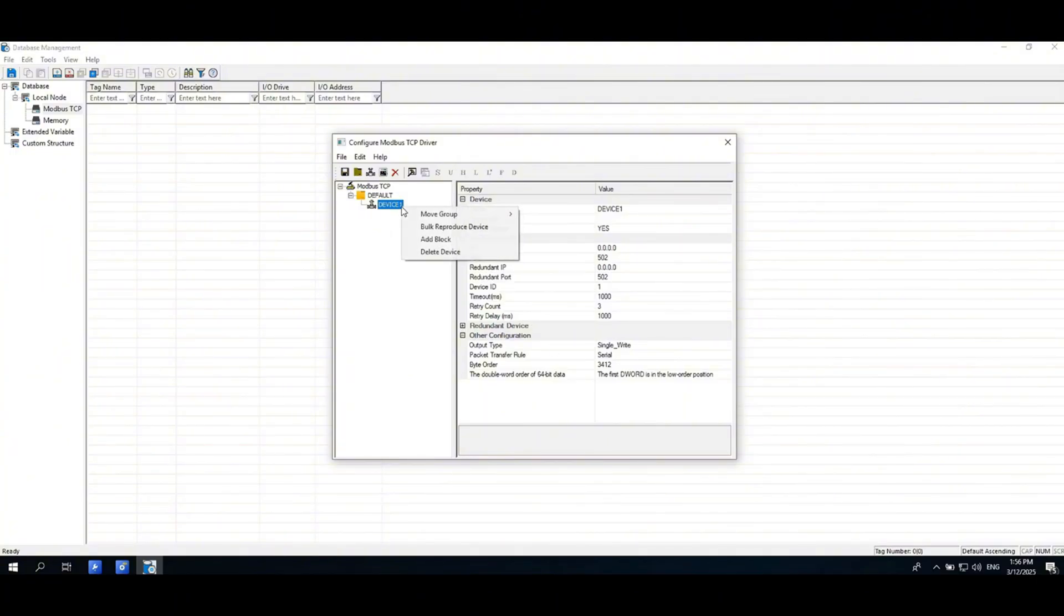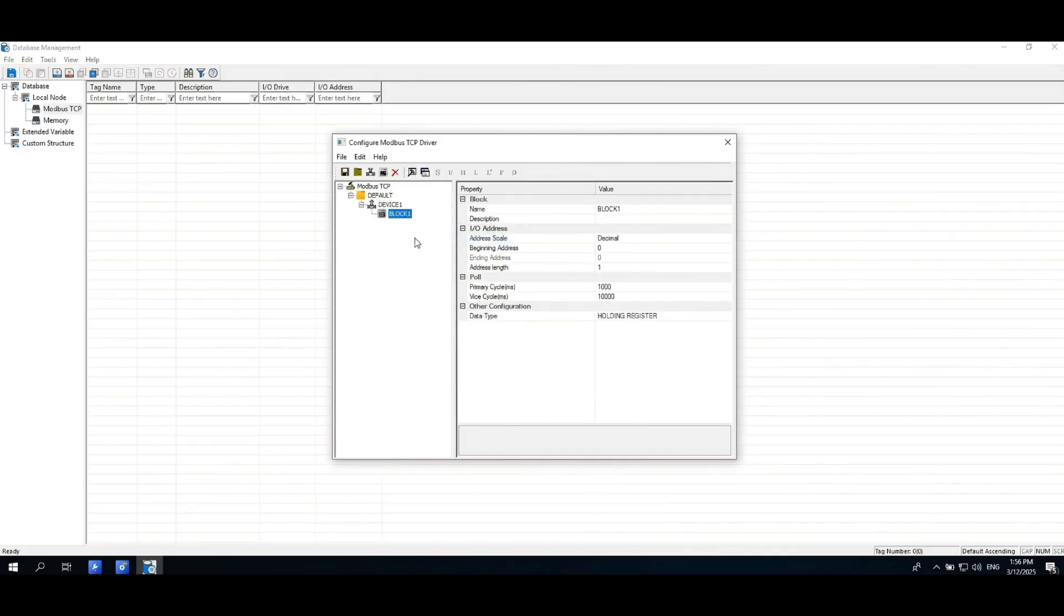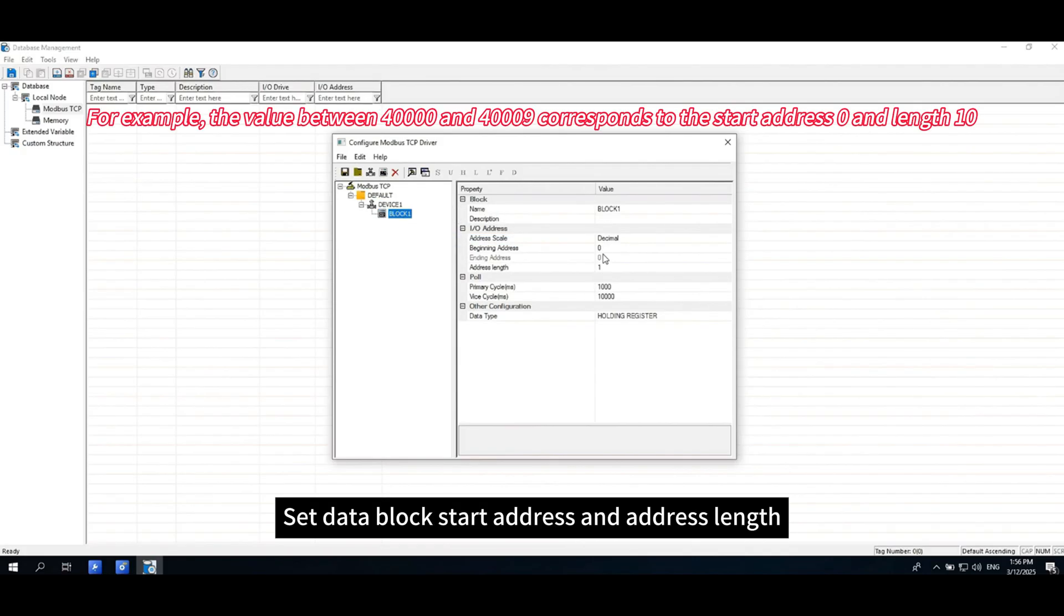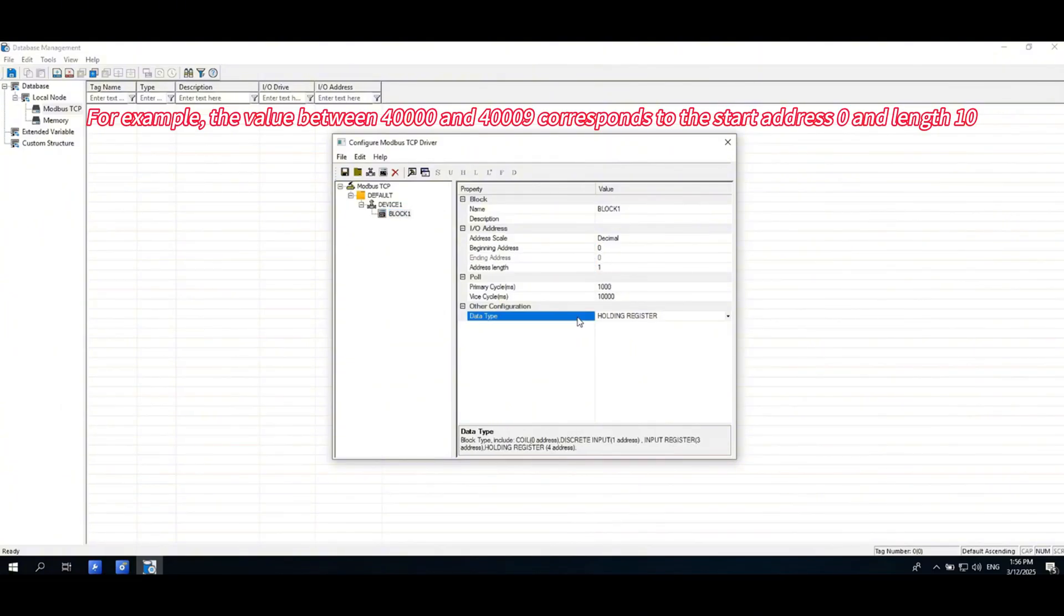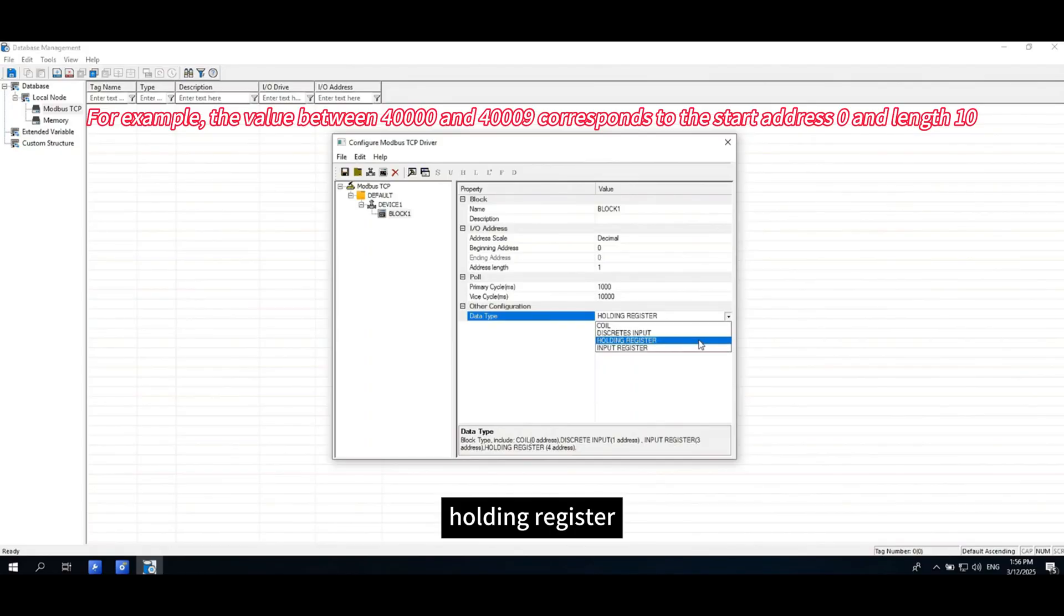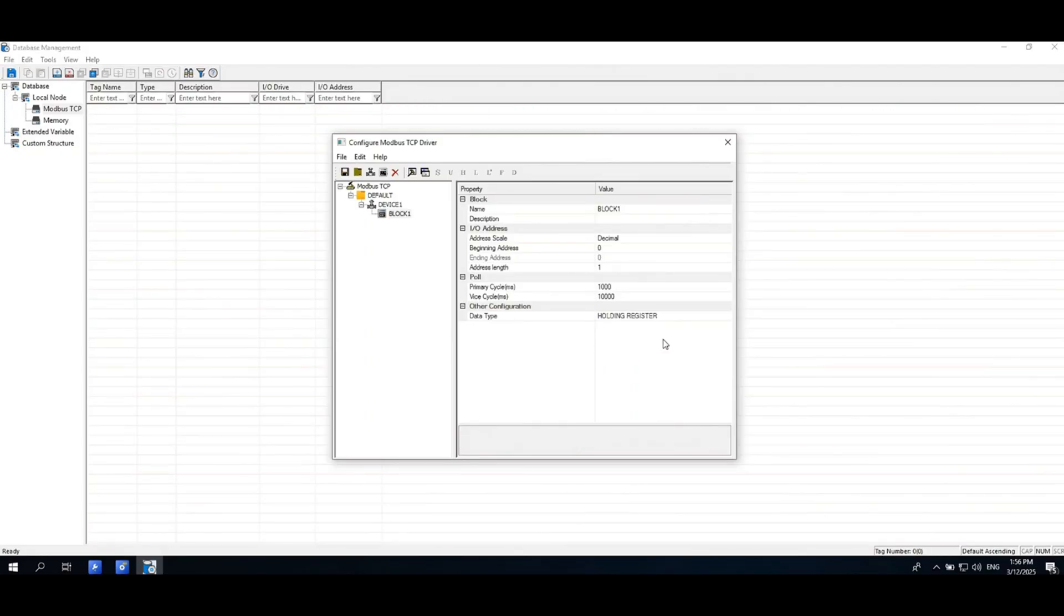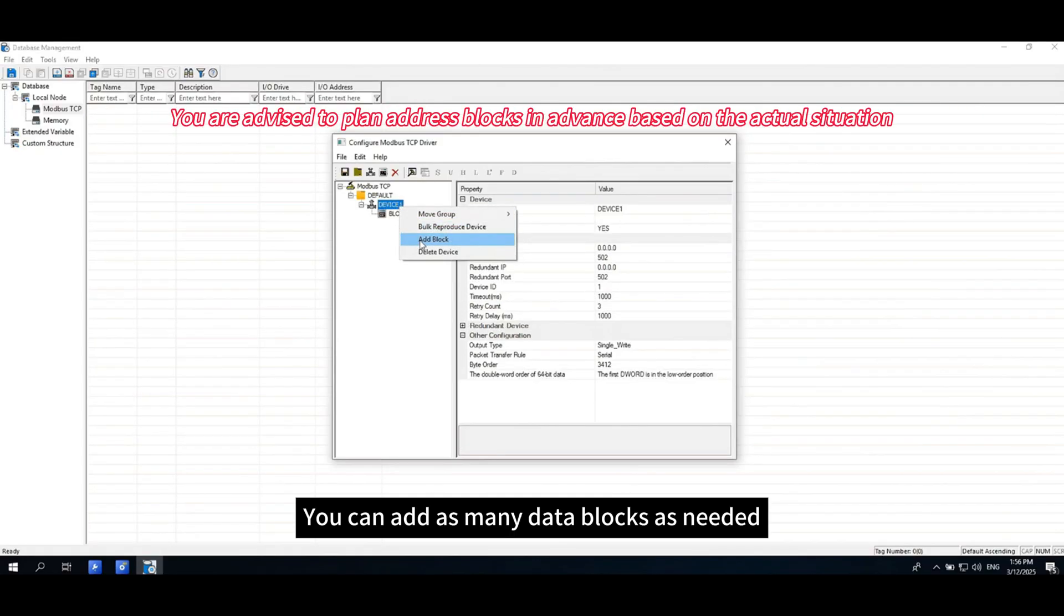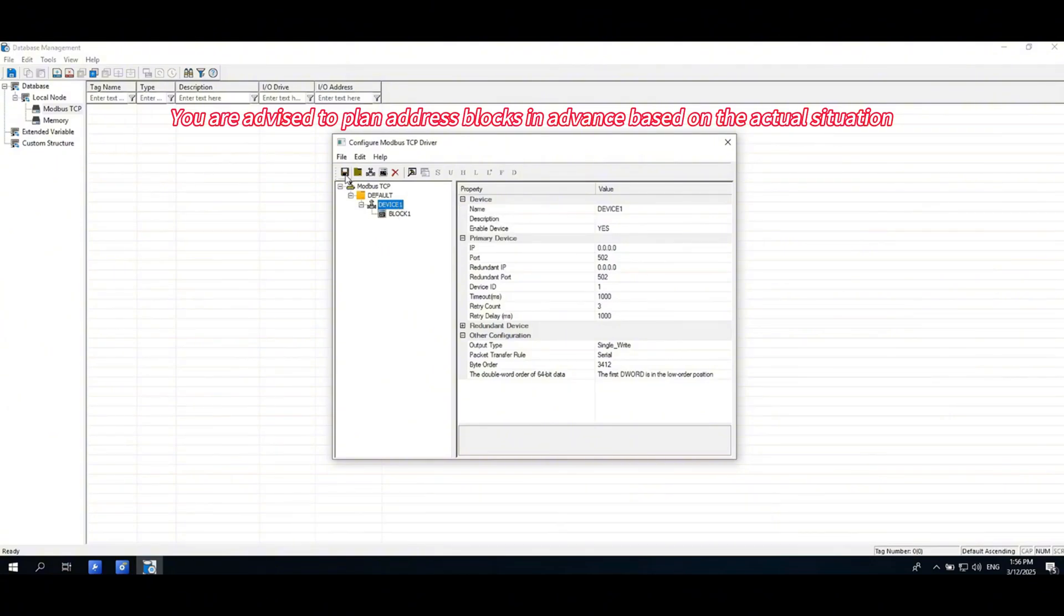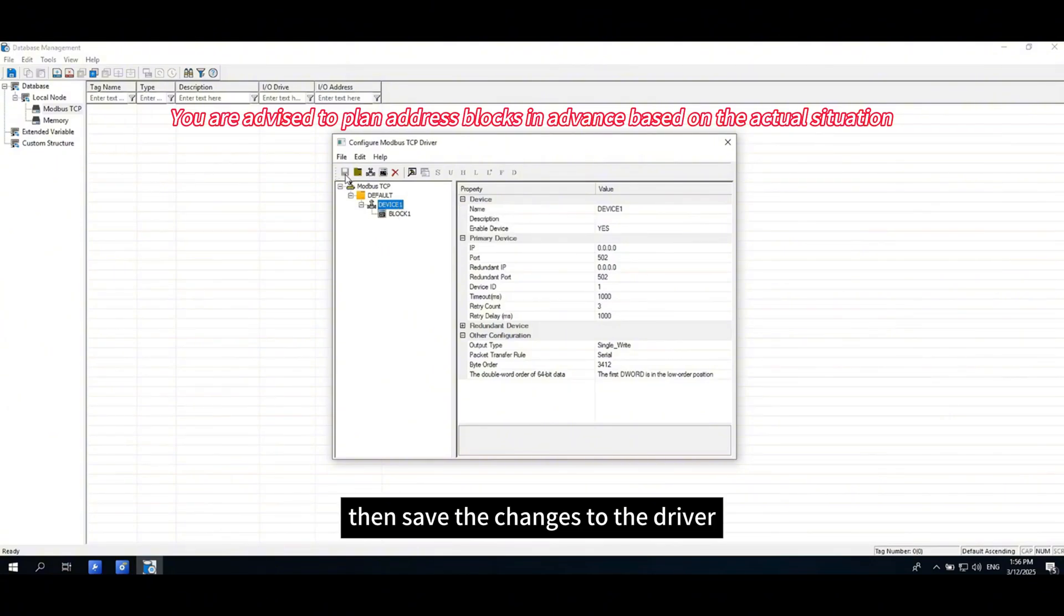Then add the data block. Set data block start address and address length, data type, holding register. You can add as many data blocks as needed, then save the changes to the driver.